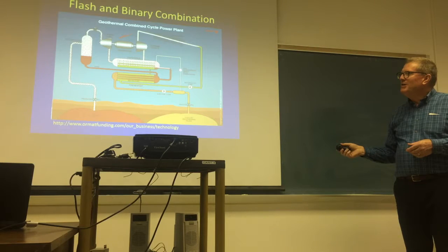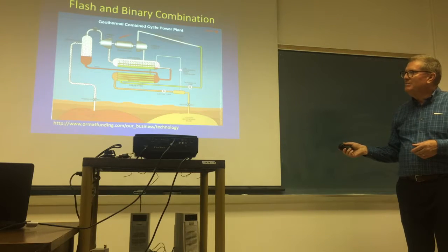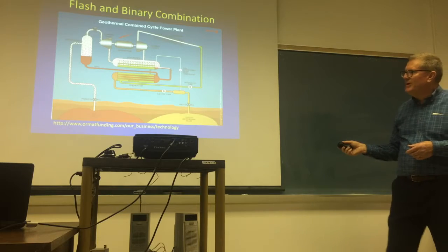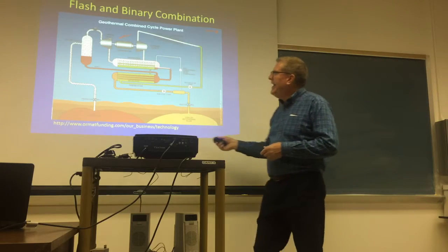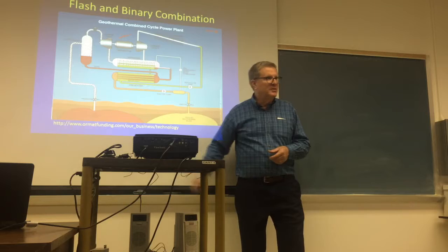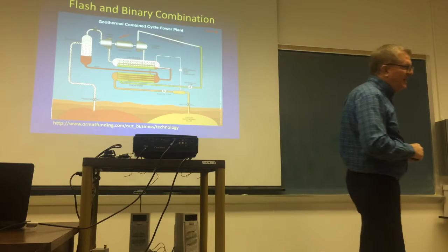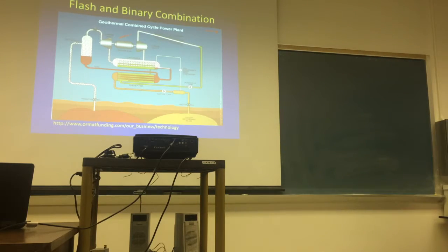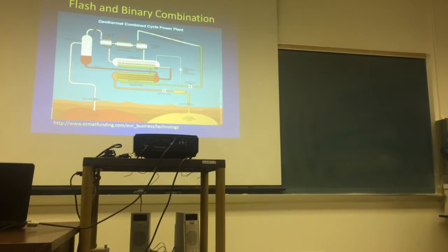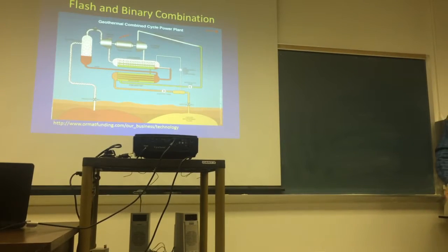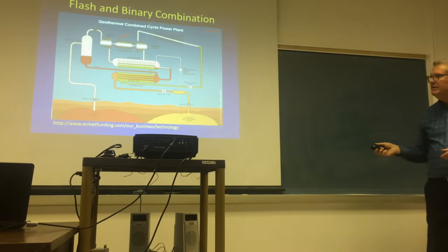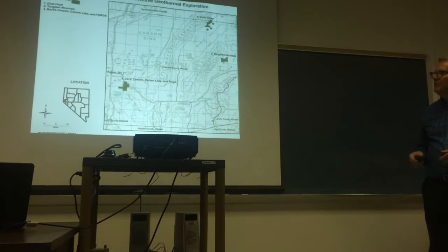And there are some hybrid systems where, with time, as the flash systems' reservoirs cool, they actually added binary systems onto the back of them - those are called bottoming units. If you pass on Brady's Hot Springs on I-80 east of Fernley, that's actually one of those - an old flash plant where they added a binary plant to the tail end and brought the output of electrical energy back to its original value. So they're getting quite crafty at this technology that's evolved over the last 30 years.